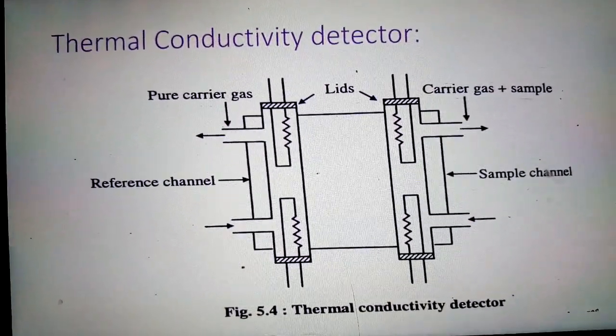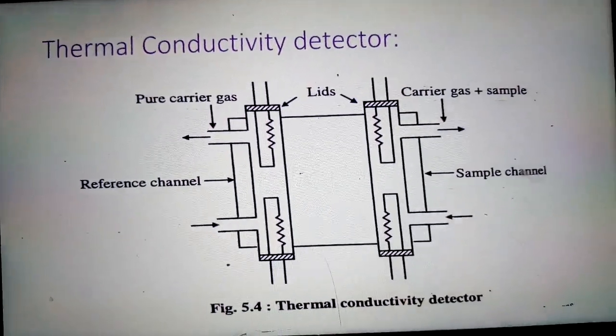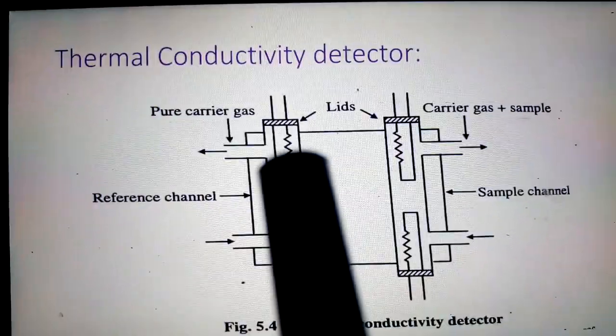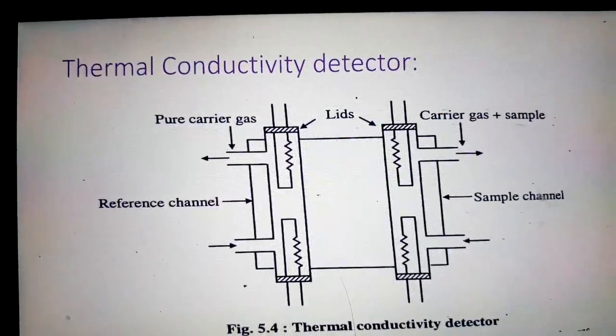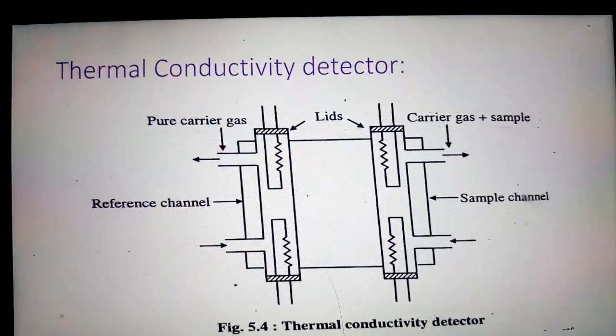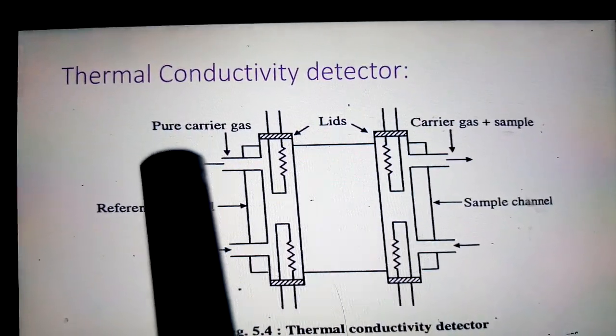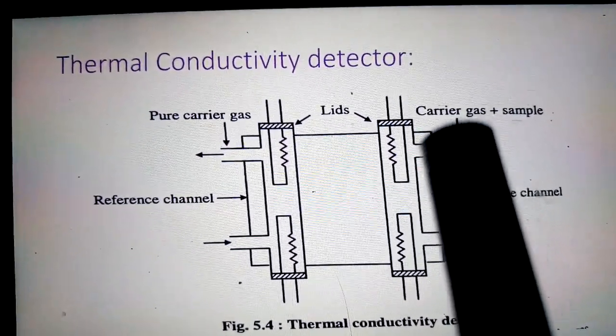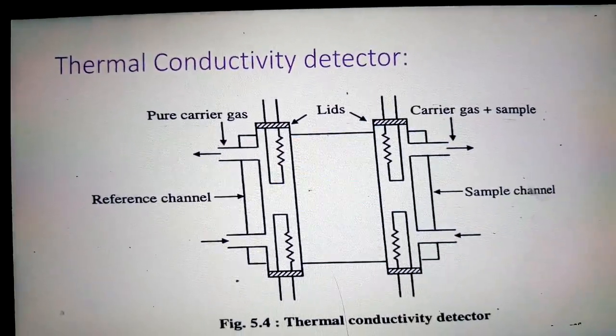In this device there are 2 pairs of matched filaments, that means there are 4 filaments. There are 2 channels: one is the reference channel and another is the sample channel. Out of these 4 filaments, 2 filaments are surrounded by the carrier gas in the reference channel, and the other 2 filaments are surrounded by carrier gas plus sample in the sample channel.